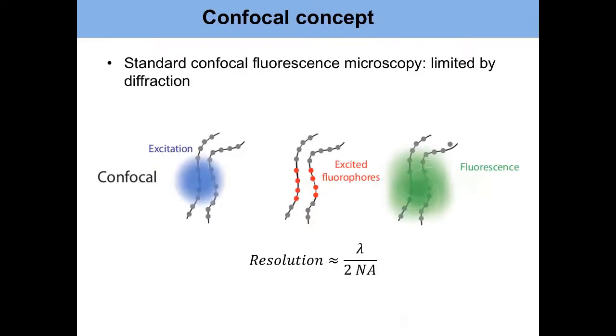So, to go a step back and explain STED microscopy. STED microscopy is a super resolution technique where effectively you start out with your confocal excitation. With a standard laser scanning confocal excitation, you're limited by diffraction, so you can only get resolution according to how tight you can focus your light. If you're scanning your light over a sample, you're going to excite multiple fluorophores, and then you'll see this smeared out fluorescence, and your resolution is determined by roughly the wavelength over 2 numerical aperture.